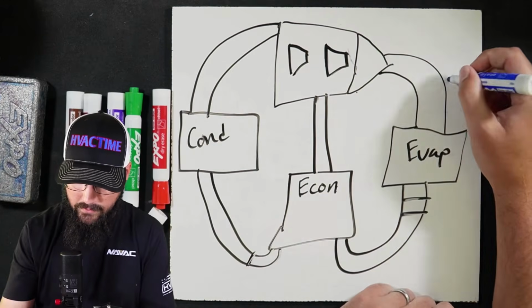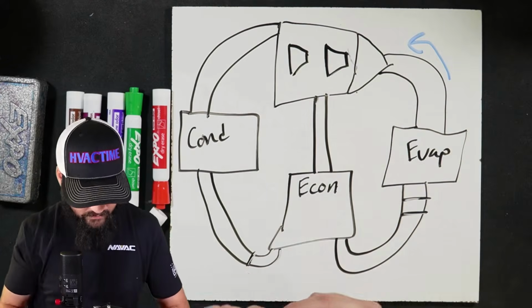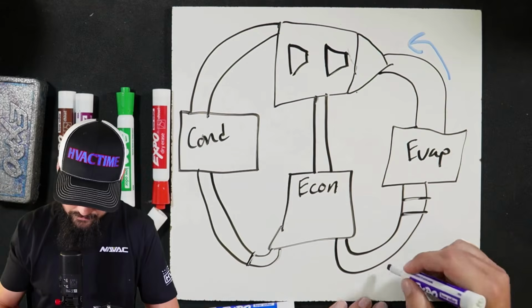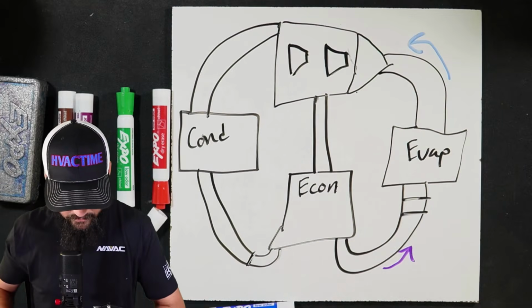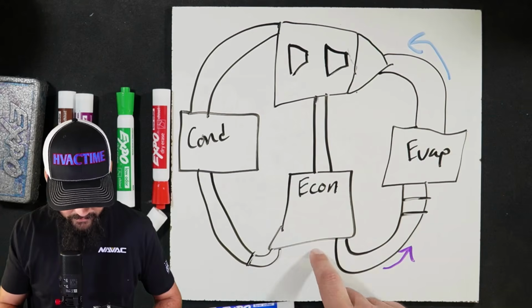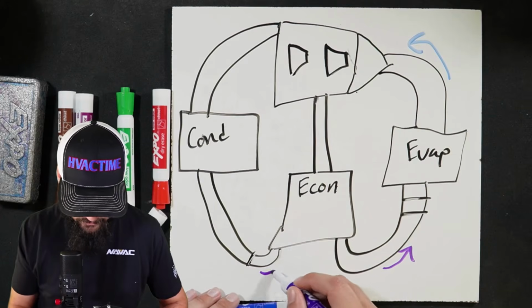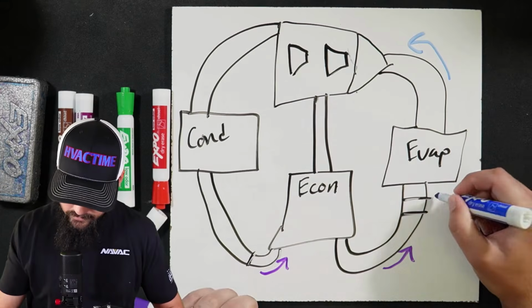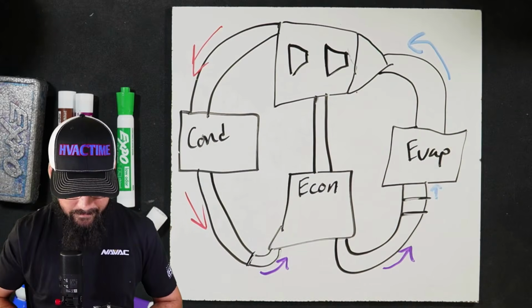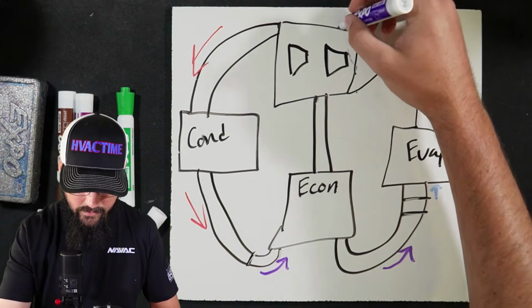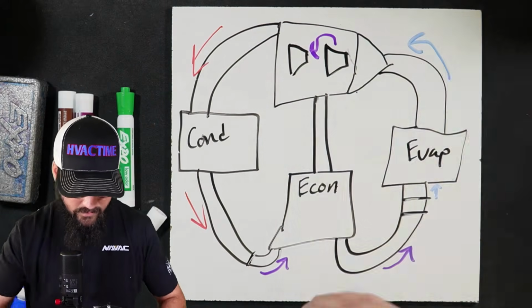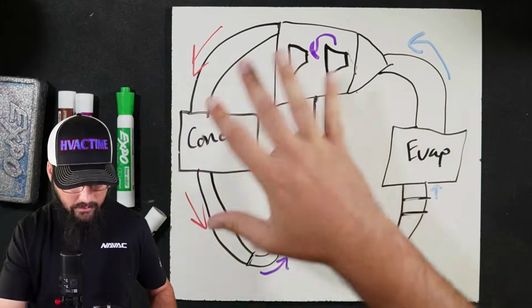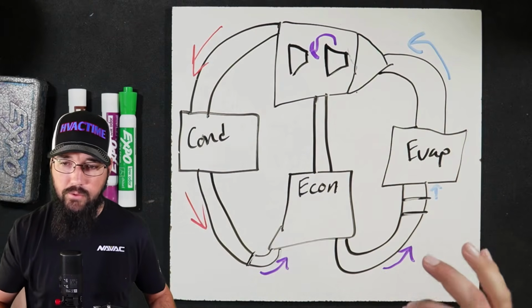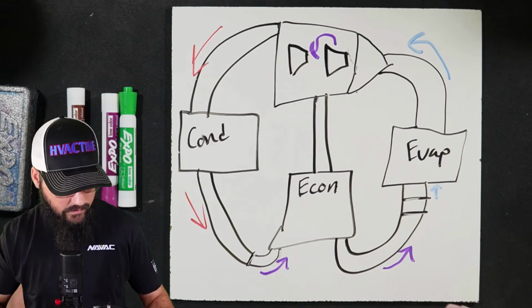Let me get some color involved here so you kind of see the process. So we're going to have low pressure. Purple is going to be our medium pressure. We've actually got 2 medium pressures here. Well, this one doesn't have an internal. So yeah, this will work. Going to be purple here. Right here is going to be low. And then we're going to do red, high pressure. And then here in the compressor, we have medium pressure coming in. So low pressure coming in, medium pressure. This is the basic refrigeration cycle for our Trane CVH series or CDH.